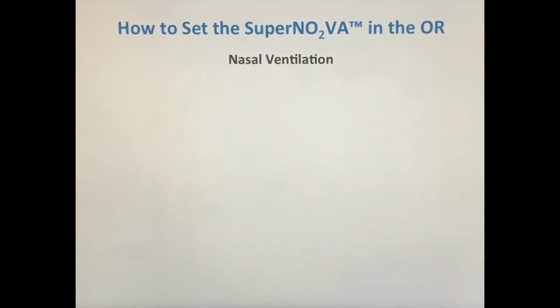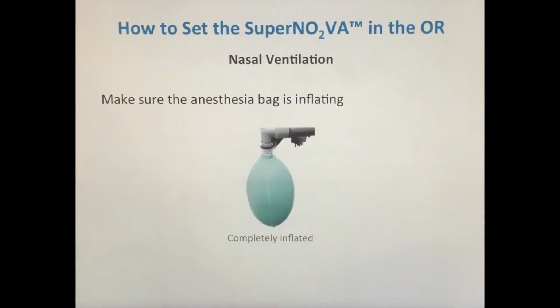Next, we have to make sure that there is no leaks in the system. In order to do so, look at the anesthesia bag. Make sure that the anesthesia bag is completely inflated. This will ensure that there are no leaks. If the anesthesia bag does not inflate, the first place to check for a leak will be around the SuperNO2VA.